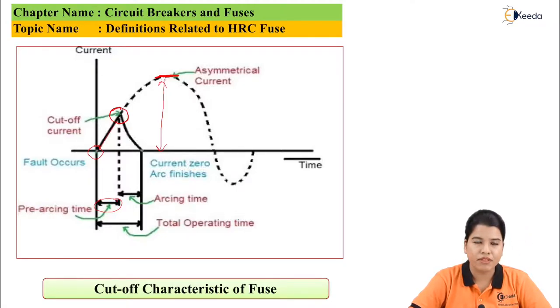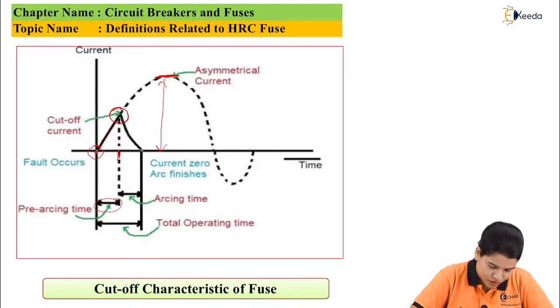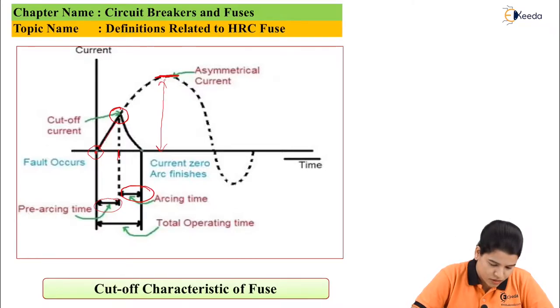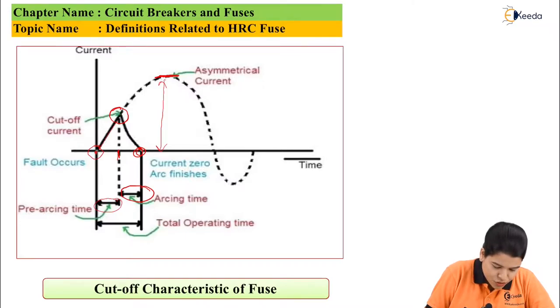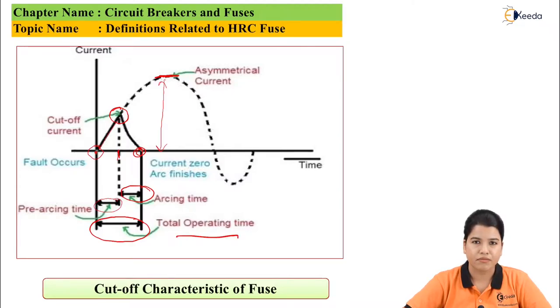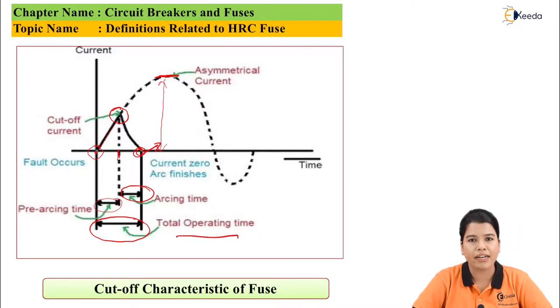This is the pre-arcing time — that is the time between commencement of fault up to the cutoff. This is the arcing time — that is the time from cutoff to the current zero position. The addition of the arcing time and pre-arcing time is the total operating time. This point shows the current zero where the arc is finally finished.